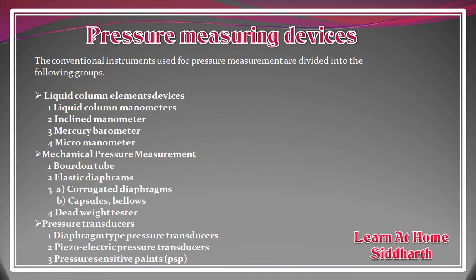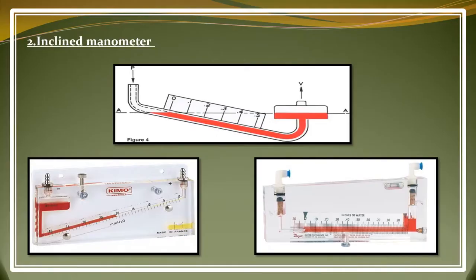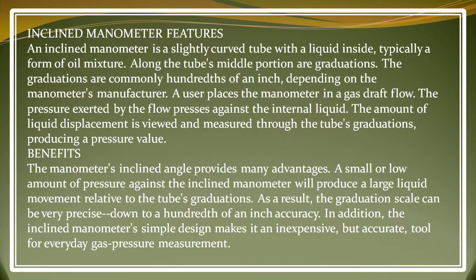The second device is the inclined manometer. As you can see in the figure, an inclined manometer is not very different from a U-tube manometer. The basic difference is that one leg is inclined. This allows us to measure a small pressure difference with better response. An inclined manometer is a slightly curved tube with a liquid inside, typically an oil mixture, along the middle portion with graduations commonly in hundredths of an inch depending on the manufacturer.